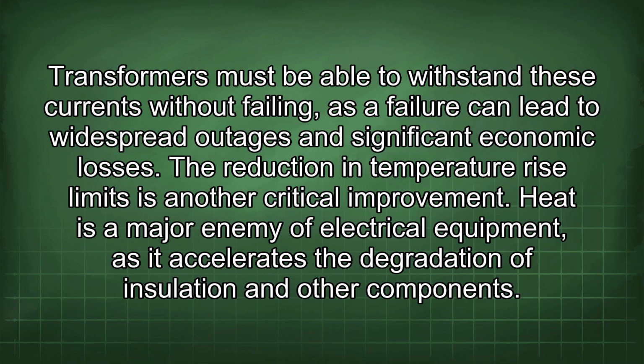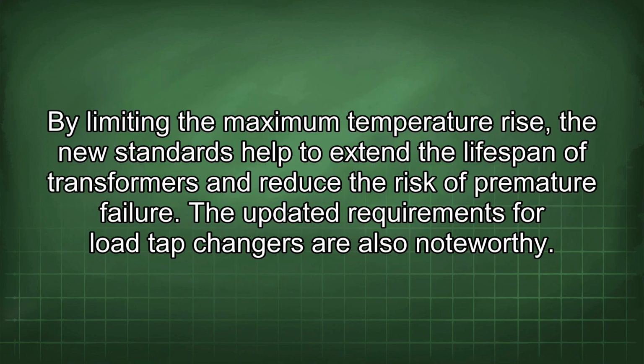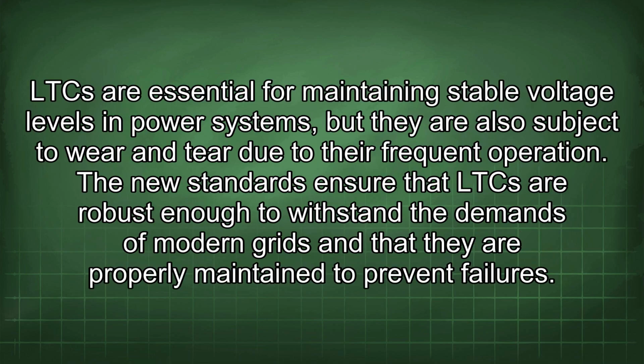Heat is a major enemy of electrical equipment, as it accelerates the degradation of insulation and other components. By limiting the maximum temperature rise, the new standards help to extend the lifespan of transformers and reduce the risk of premature failure. The updated requirements for load tap changers are also noteworthy. LTC are essential for maintaining stable voltage levels in power systems, but they are also subject to wear and tear due to their frequent operation. The new standards ensure that LTC are robust enough to withstand the demands of modern grids and that they are properly maintained to prevent failures.